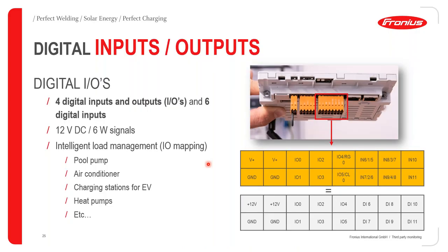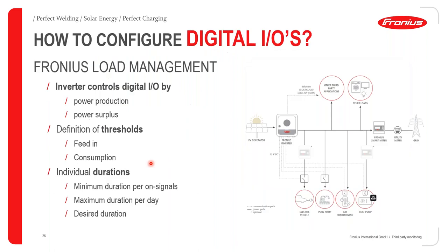Looking at the digital input/output ports: there are four free digital input/output ports, 12 volts DC with a power capacity of 6 watts, that can be used to intelligently manage loads. These loads could include pool pumps, air conditioners, control ports for EV charging stations, and heat pumps.